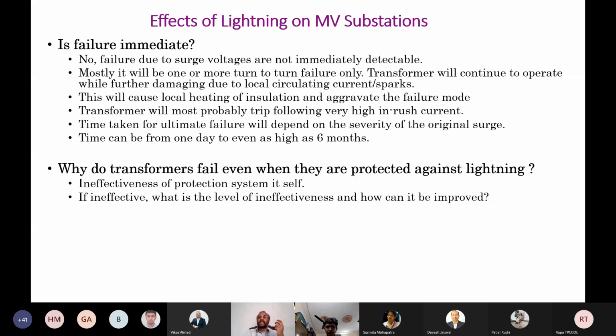Then why do transformers fail even when they are protected against lightning? This is another very important question that many people ask. People think that they give protective measures, but unfortunately, if you do not consider the whole scenario comprehensively, for example, if you have very good surge arresters, but your earthing system is not properly done, or you have improved the earthing system very nicely, but your surge protectors are not good, or you have both surge protectors and earthing system very good, but your connection is done erroneously. Then, especially in medium voltage substations where there is a delta to star connection, it's very important to decide regarding the connection of the earthing systems and so on. And this is a very important point.